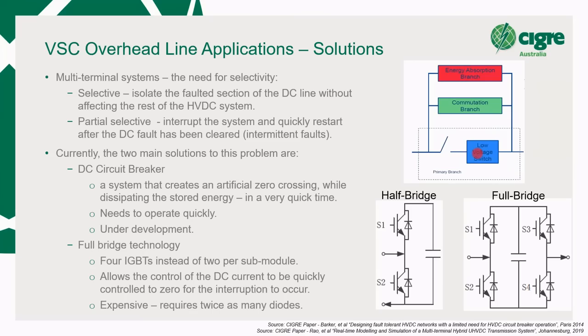So here, when a fault is detected, the commutation branch, which is a power electronic device, but it's not always in the circuit, will deblock and commutate. And at the same time, we block this low voltage switch. That basically diverts the current enough so that we can open this high-speed DC switch. In addition, you also have an issue where you've got all this energy that you have to get rid of. And so the current designs are looking at putting in an energy absorption branch, which is basically a bank of arrestors to get rid of that energy as quick as you can. These things aren't expected to operate very often. They will, of course, then reclose back in, but that's pretty much the design that's being used.